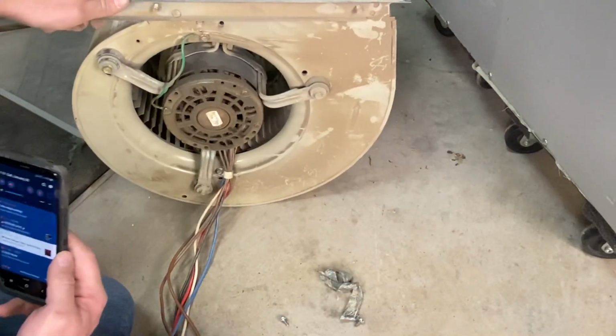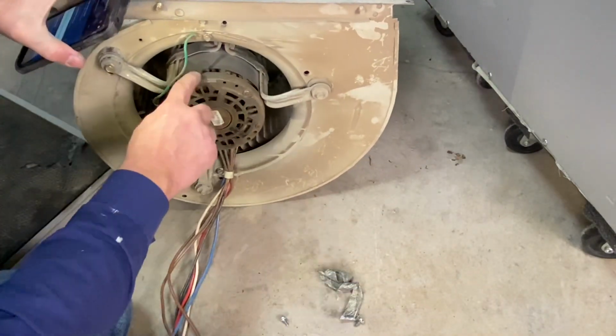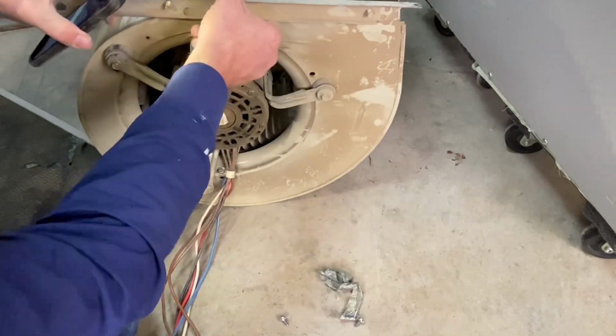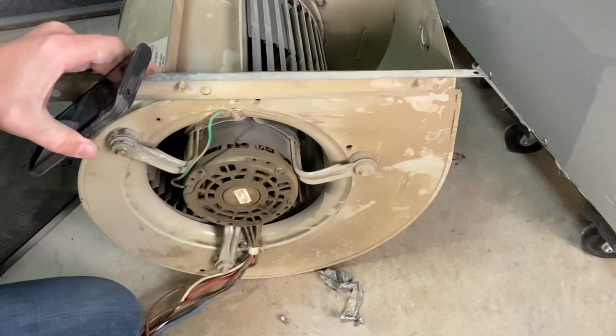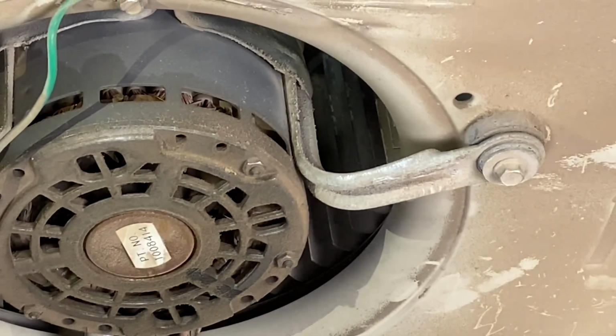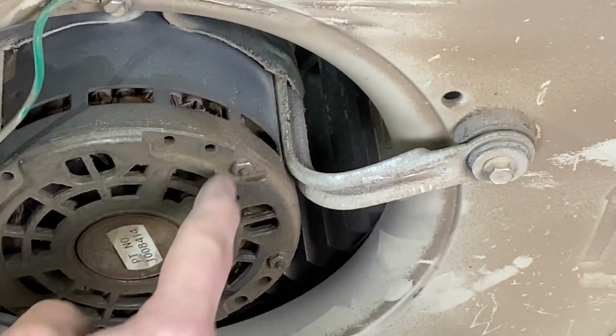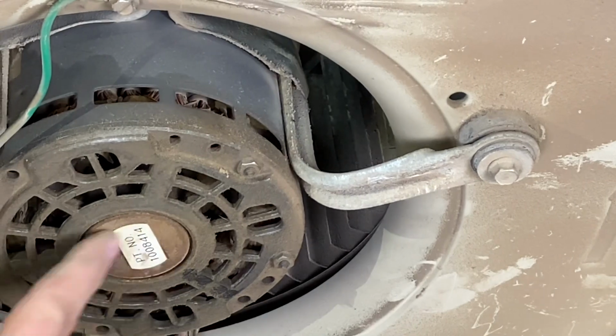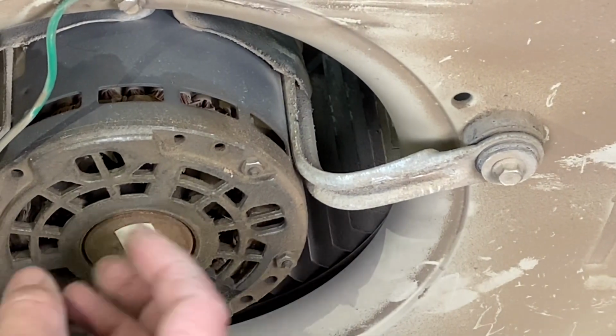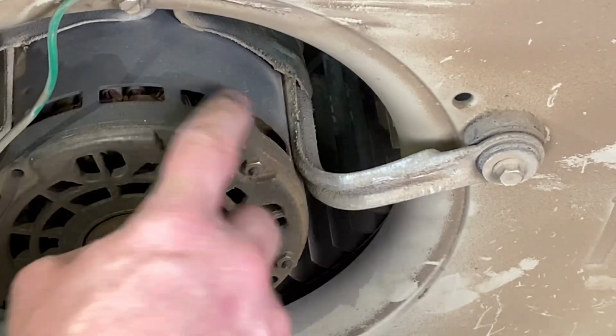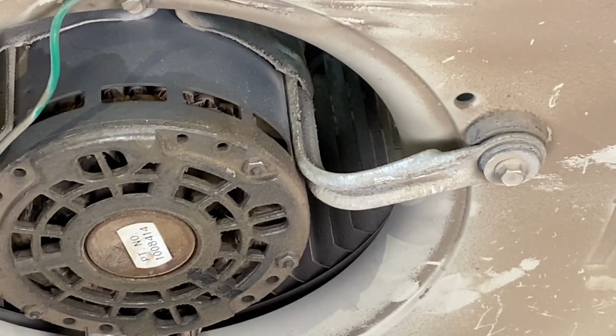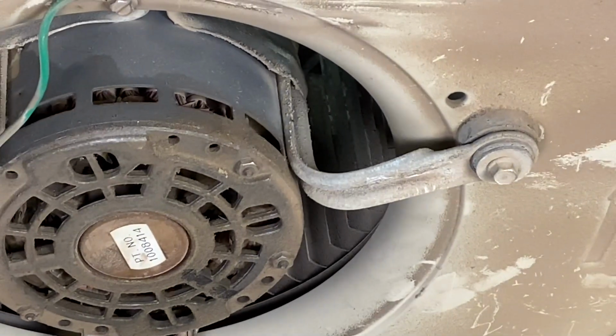This is our blower motor. Some of the things that we see about this motor is there's this little bit of a stain right here. We'll zoom in so you can see that a little bit better. This oil stain is because these are sealed bearings. They're sealed for the life of the unit. Over time, this oil starts to come out of the bearings, and that's what's causing the stain on here. So it's probably a matter of time before this blower went out anyway.